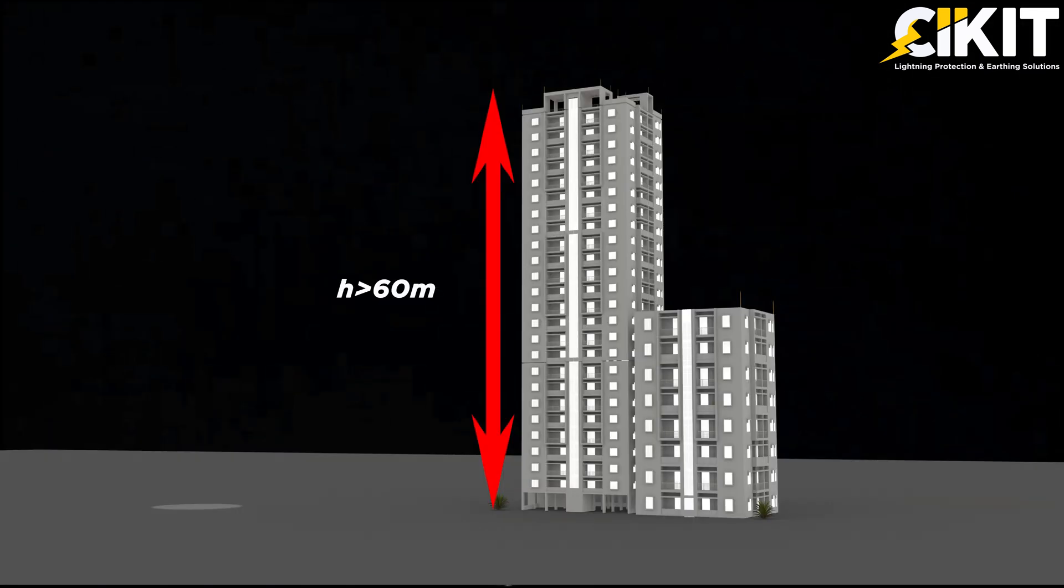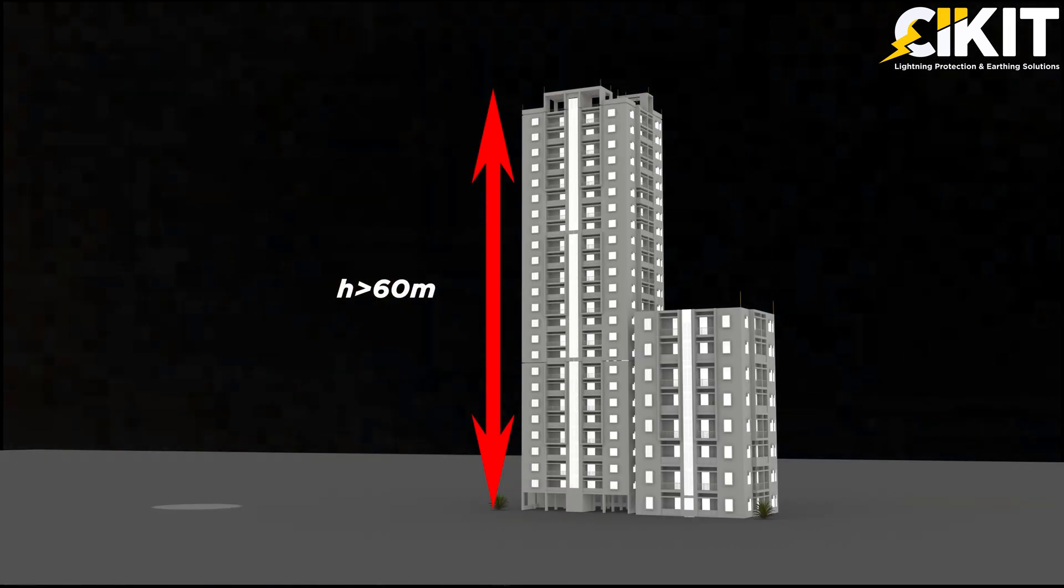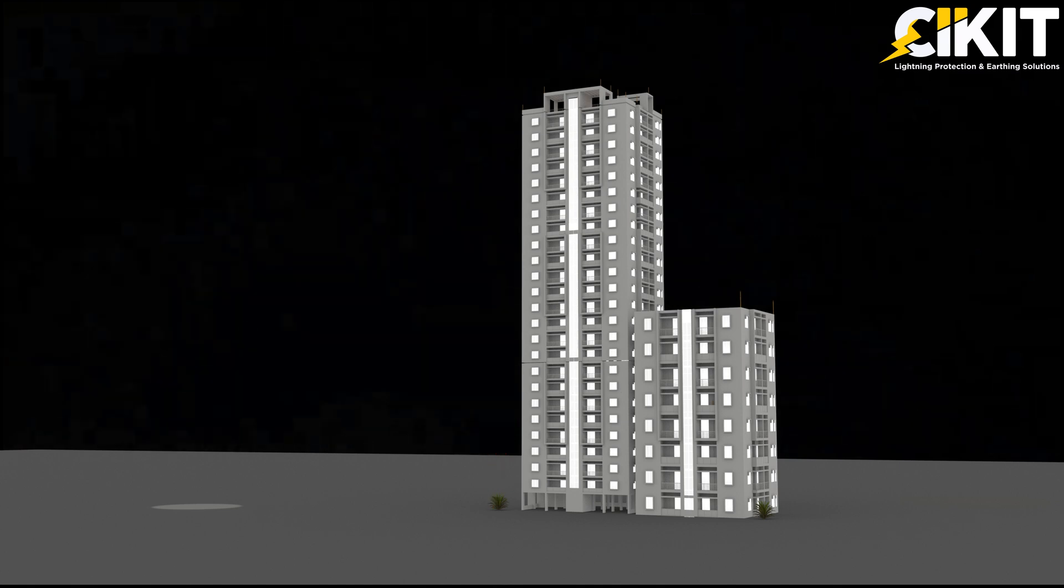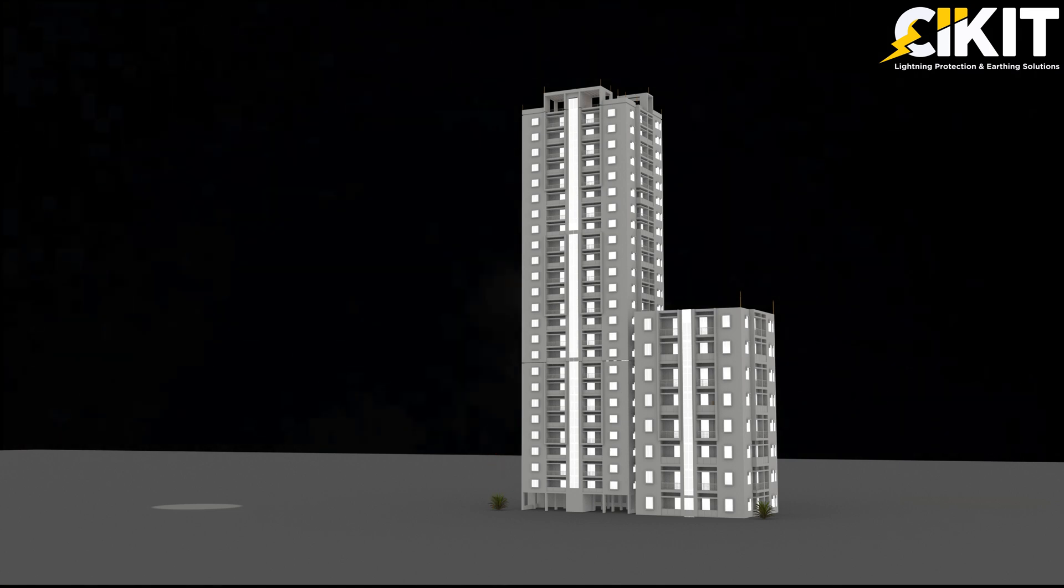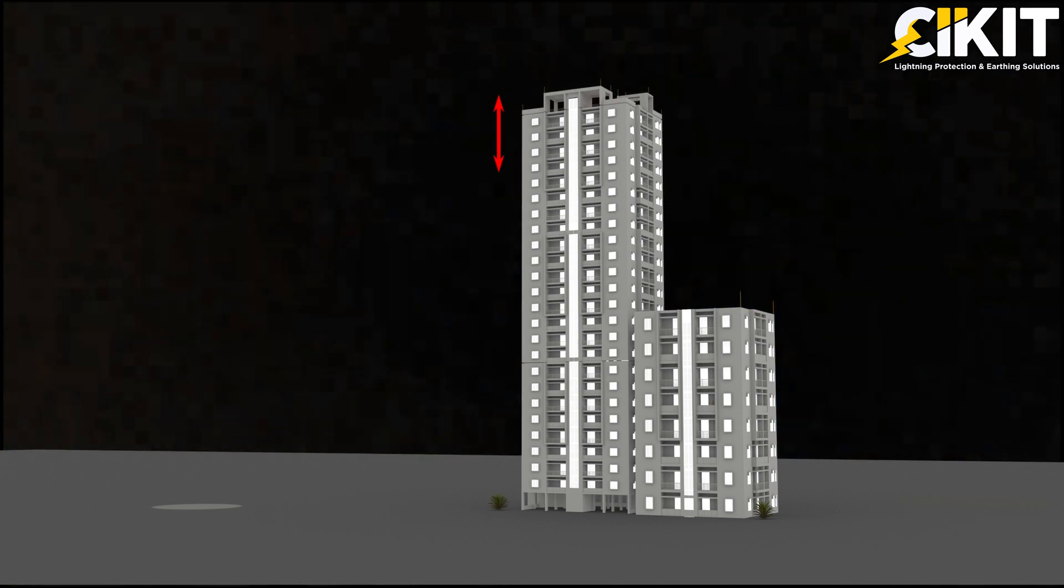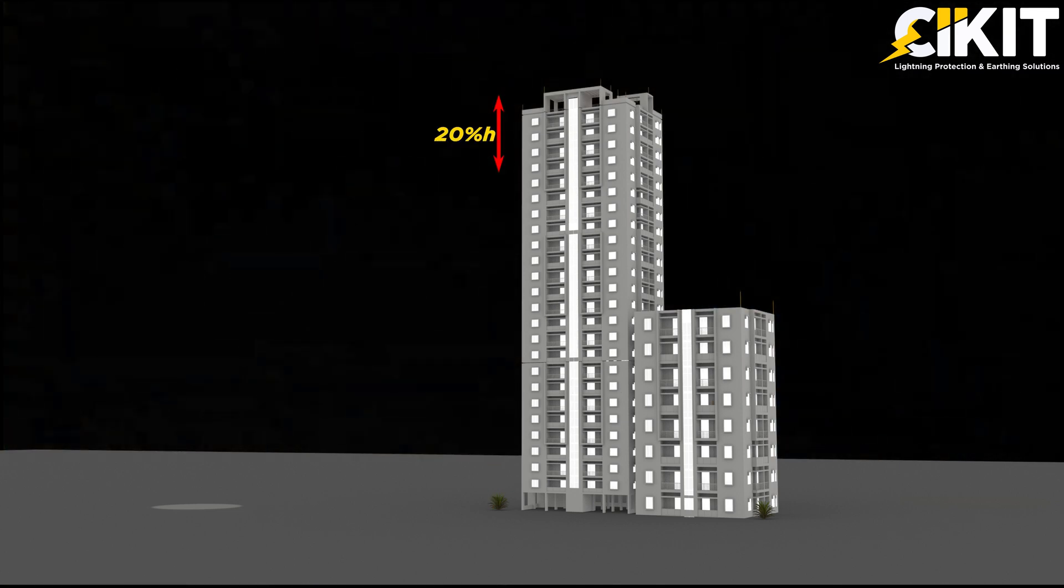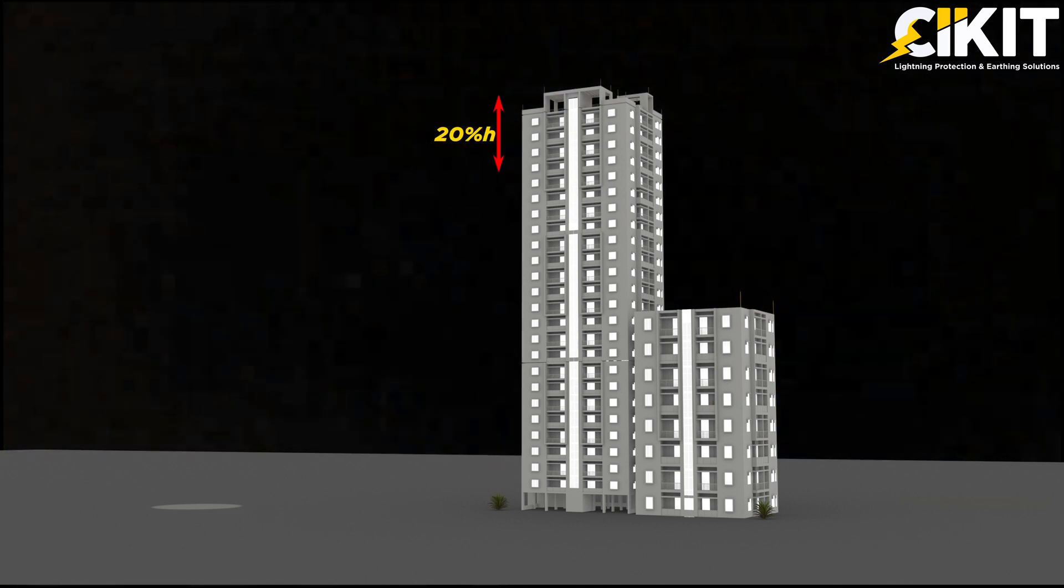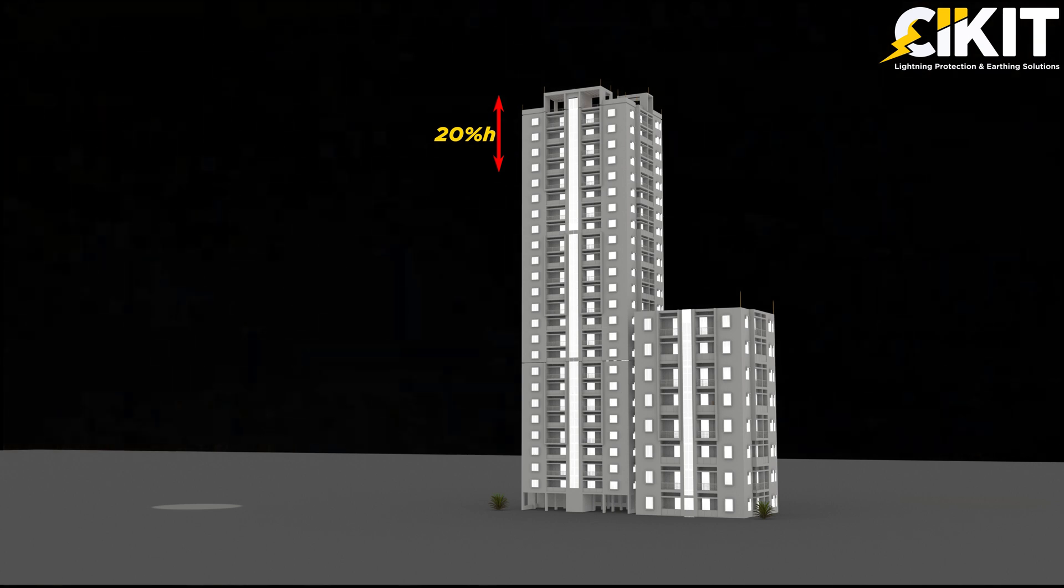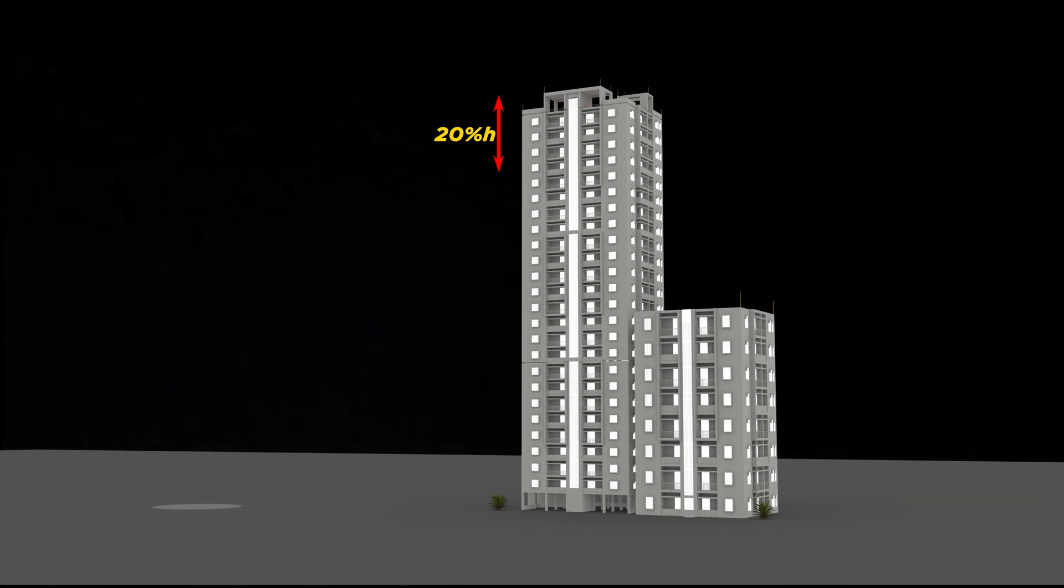For buildings of height greater than 60 meter, an additional protection should be provided for the top 20% of the height by using lateral air termination system.